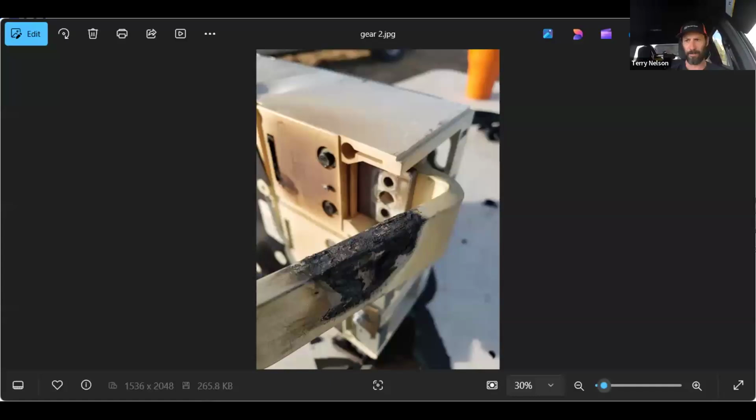So here's an example of a breaker that had a catastrophic failure. What happened is that's the bussing on the back of the breaker where it attaches to the switch gear. Might be a little bit over your guys' head, but this is like an 800 amp breaker. So there's a lot of current rolling, and the connection was fine, but the equipment wasn't able to dissipate the heat enough. They had not vented it properly, and so it was just building heat, and all that heat was stacking up, started melting metal.